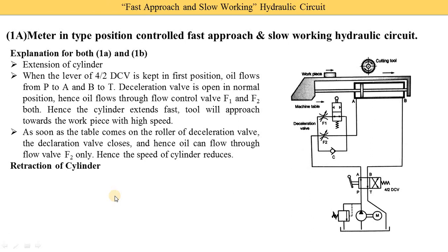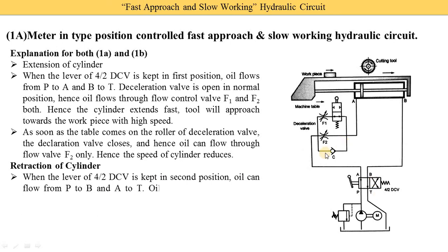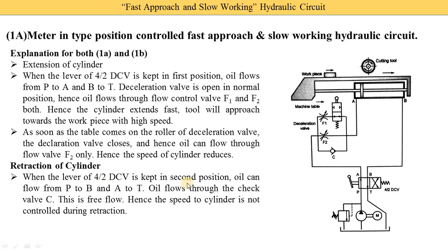That completes the extension stroke. For the retraction stroke, the operator changes the position of the directional control valve. When the lever of the 4/2 DCV is kept on the second position, oil flows from P to B and A to T. Oil from the pump is supplied to the B-port and then to the cylinder, moving the piston from right to left. Oil on the left side of the piston comes to the A-port, where it has three options: F1, F2, or check valve C. Since F1 and F2 are closed during retraction, oil passes through check valve C to the A-port, and from A to T to the reservoir. This is called free flow; hence, cylinder speed is not controlled during the retraction stroke.